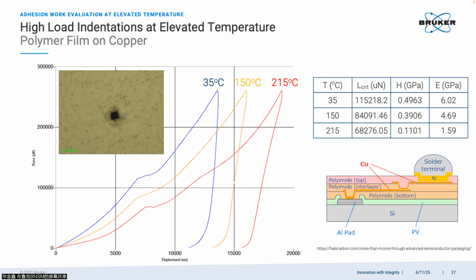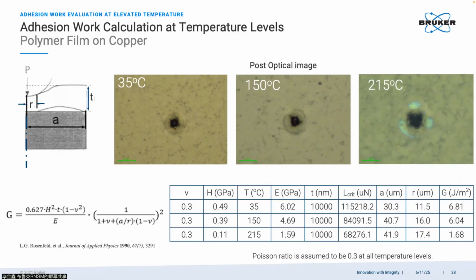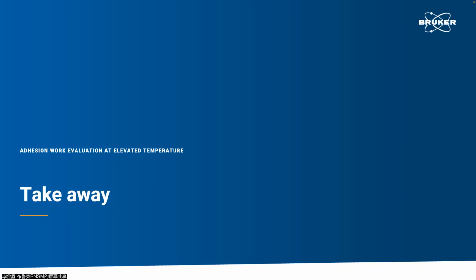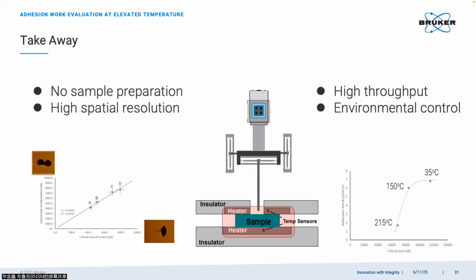For indentation tests, the force range is from maybe several tens of nanonewtons to millinewtons or even to newtons. But for AFM, typically you will see the unit of piconewton, but not nanonewton. So I would say these two metrologies, these two product lines, are both very good, but the ranges are different. And for indentation tests, we are always doing some damage. It's something we love to do, to damage something to expose it.